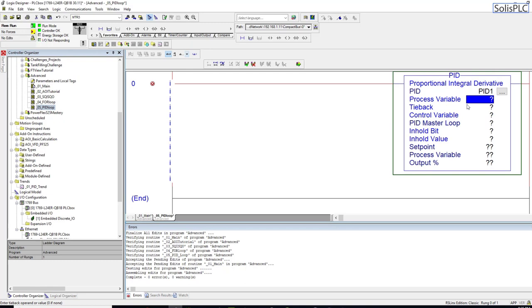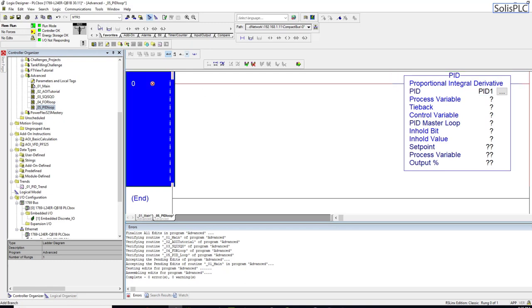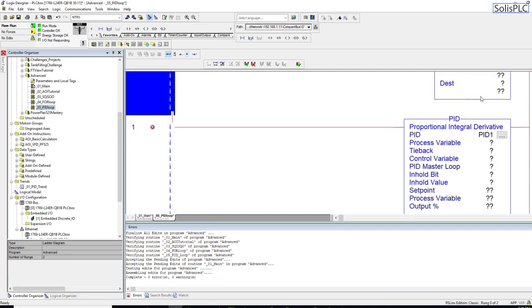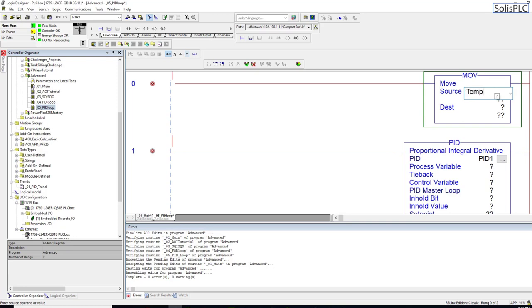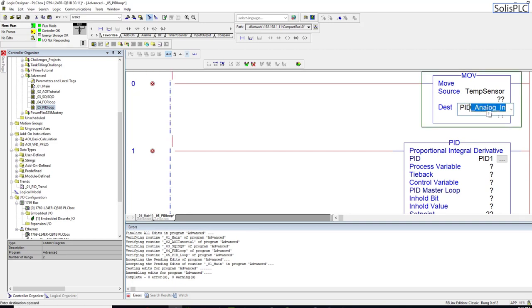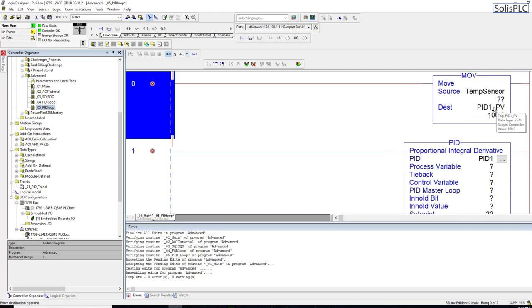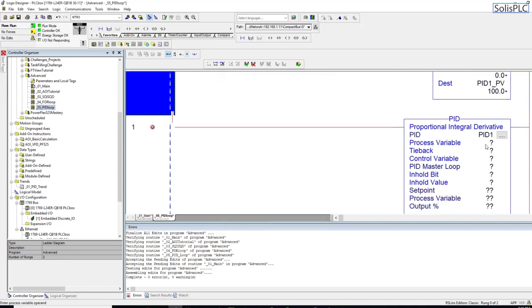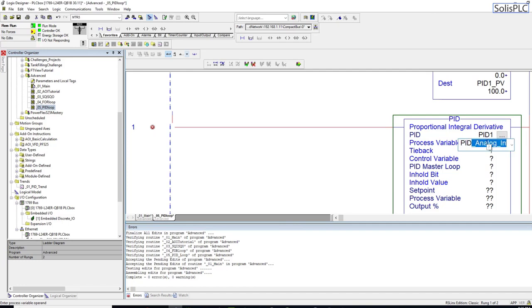We're going to need to create some process variables. The process variable is your input to the PID loop. I'm going to create a dummy rung to give us more visual on the PID loop — think of this as a temperature sensor giving us feedback from a physical device, like an analog input. This goes into PID1_PV, which is a real tag, along with a new temperature sensor real value.